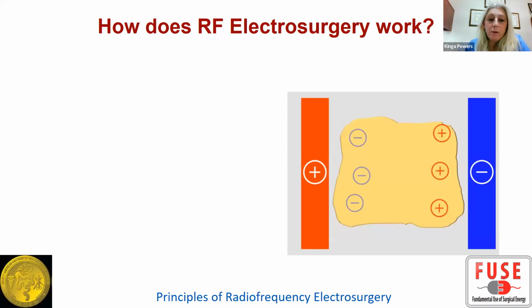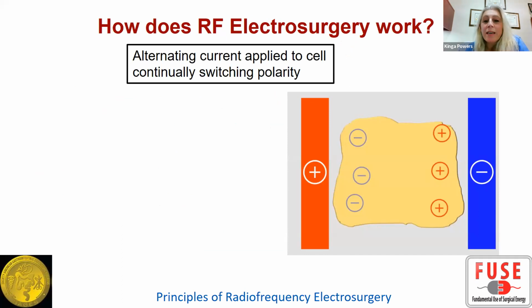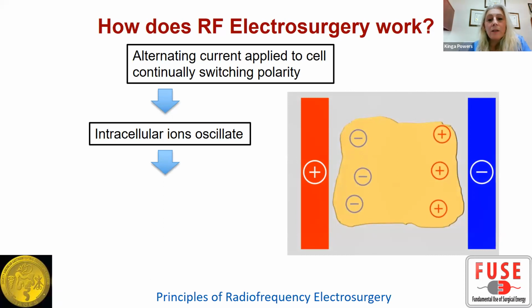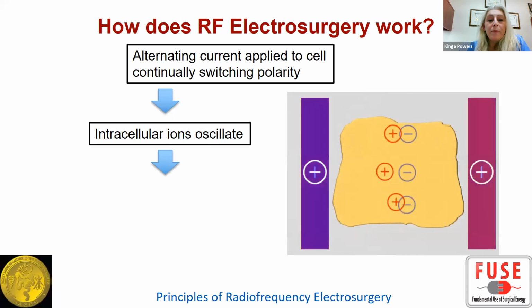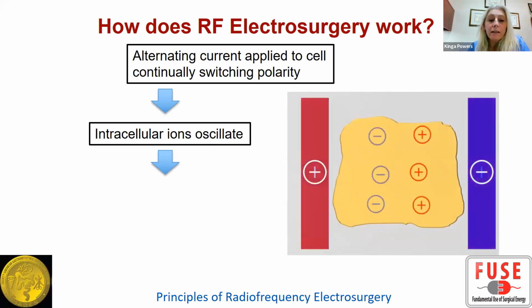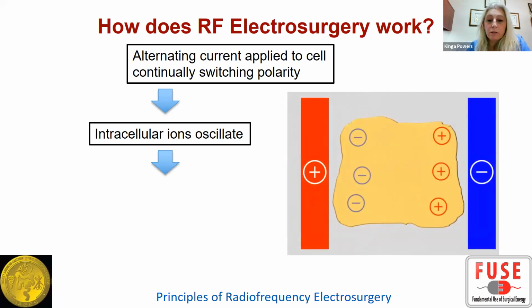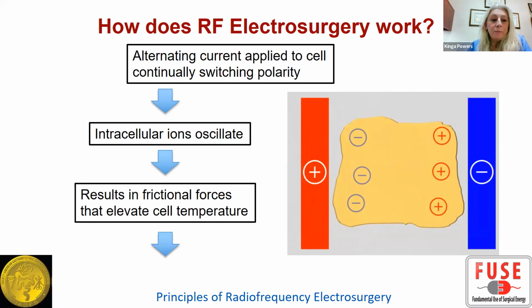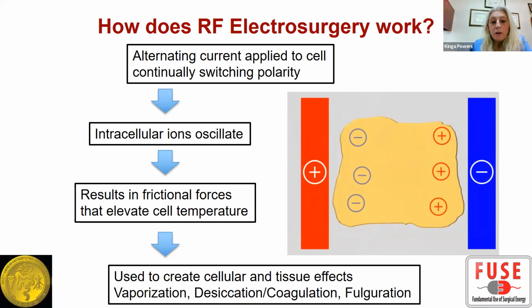So we know that an alternating current from our wall socket, in the US, is at 60 hertz. It comes out of the wall socket and is converted to the correct frequency in our electrosurgical unit, or the blue machine that is in our operating room. When this current is applied to patient tissues, it makes the intracellular electrically charged particles, including proteins and electrolytes, start to move and oscillate back and forth inside the cell, including large proteins, which results in frictional forces that occur in the cell, and that results in heat being created. So radiofrequency electrosurgery is basically the intracellular conversion of this electromagnetic energy that's applied to the cell, converted to kinetic energy and then to thermal energy.